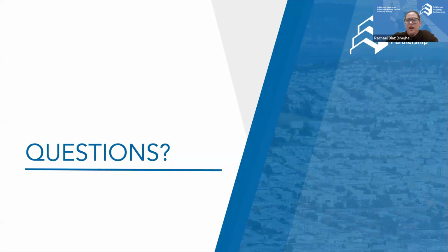Thank you both. For the sake of time, last question, but Mark, do you happen to know what the cost range for a building management system is upfront and what monthly charges are? I know it might vary by kind of choice and platform. Yeah, I mean, there's a lot of variables in the size of the building, it's a lot of times built on how many points, and a point is a data point. And so the number of points you get, you're going to increase the cost. So I've spent anywhere from $50,000 on a smaller control system to $200,000 on a larger control system. It really depends on what you're buying, and the number of points you're bringing into the system affects that change.